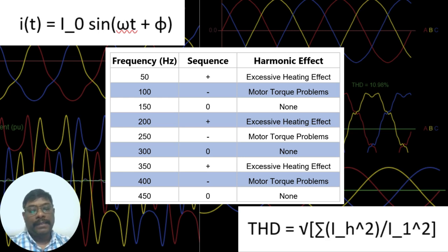The fundamental frequency, in this case a reference taken as 50 hertz, when the fundamental frequency positive sequence component increases, it produces excessive heating. That we know, when current increases, fundamental current overload or overheat causes. The second harmonic component, in this case 100 hertz, you can see it is a negative sequence component and it produces motor torque problems.